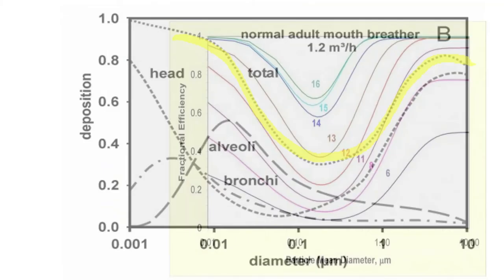In overlaying the last two charts that we looked at, you can see that human filtration mechanisms are more or less like a MERV 11 or 12 filter. It takes something higher than MERV 12 to start removing substantial amounts of materials that would otherwise get past your body's natural defenses. As such, we recommend filters that are MERV 13 or higher in performance.